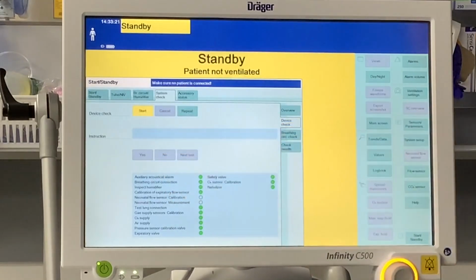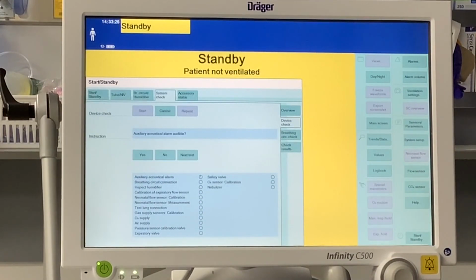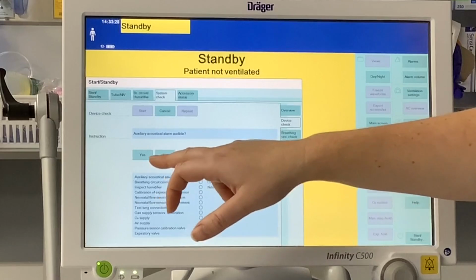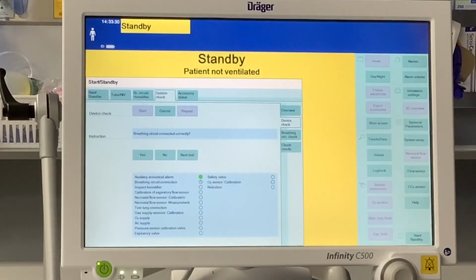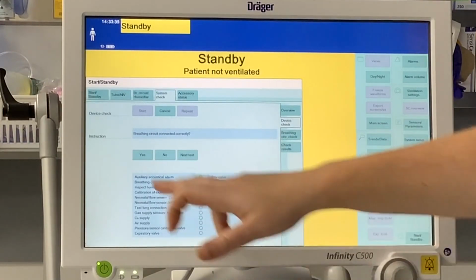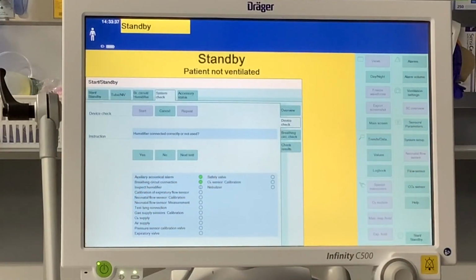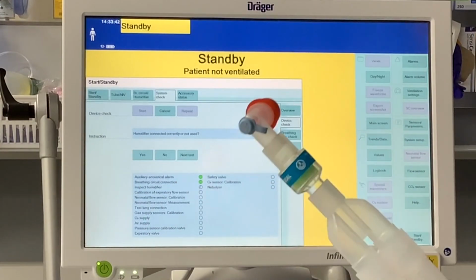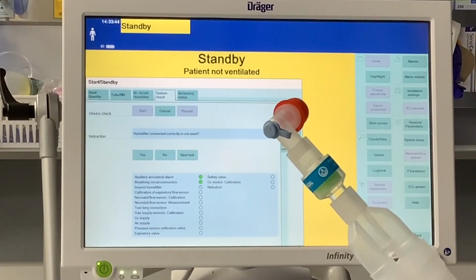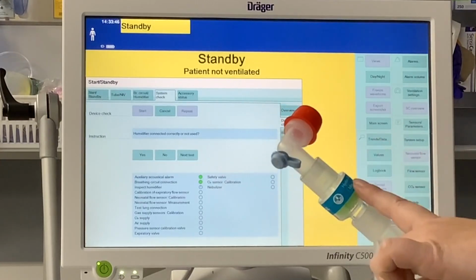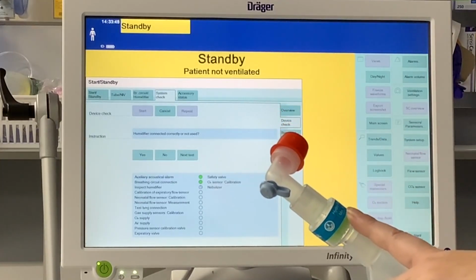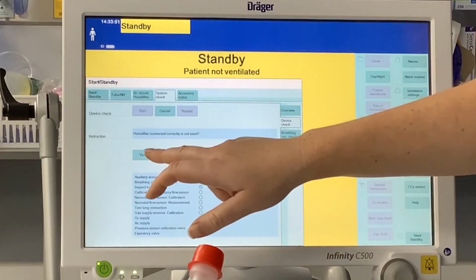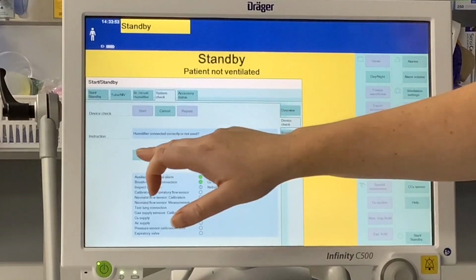I'm going to press start, click. It's going to ask us questions now. Do we hear an alarm? Yes. Is the breathing circuit connected correctly? We set that up already, so we know it is, so yes. Is the humidifier connected correctly or not used? In this case, humidifier is not used because it is a dry circuit. We always have an HME in line, but we will put yes to this. Just know that it's not used.